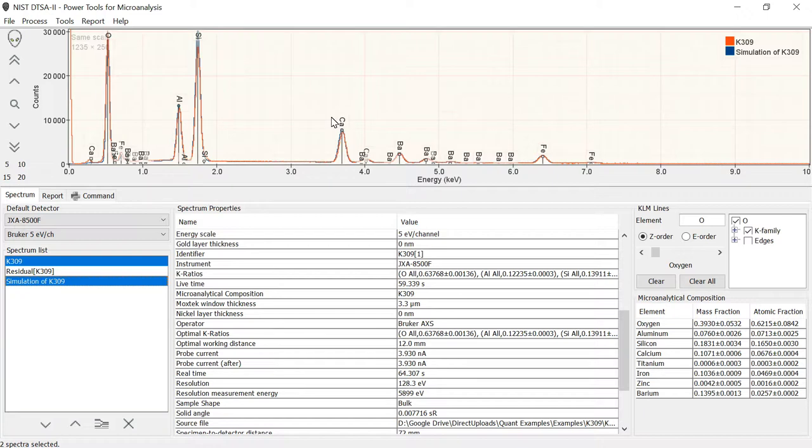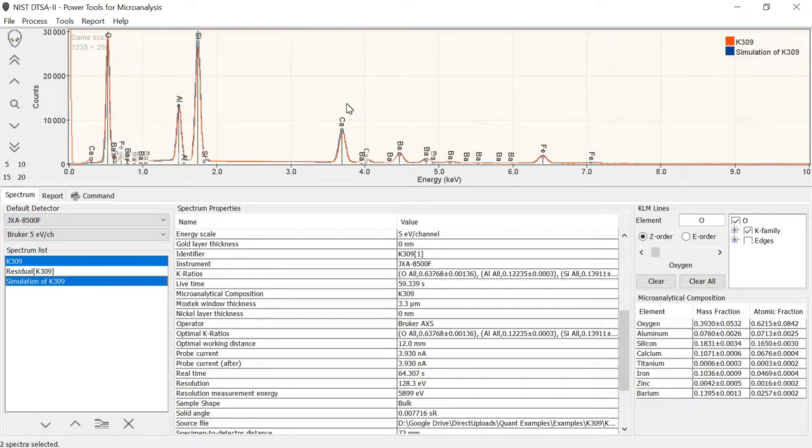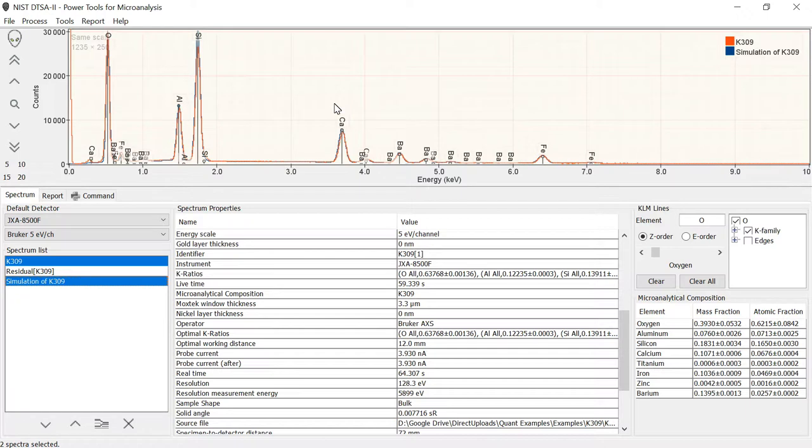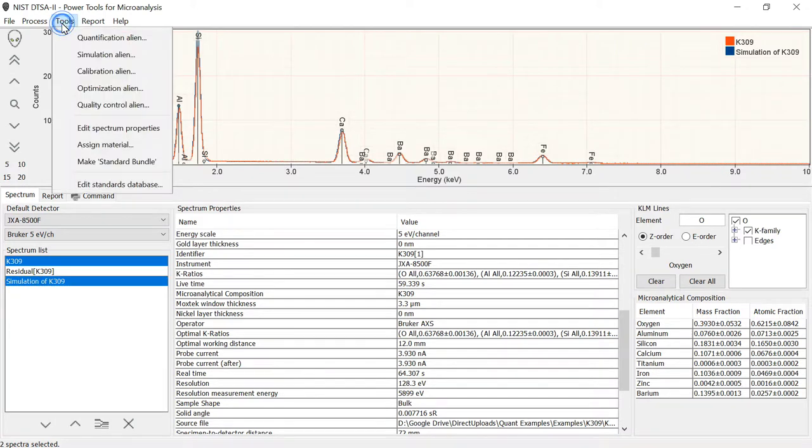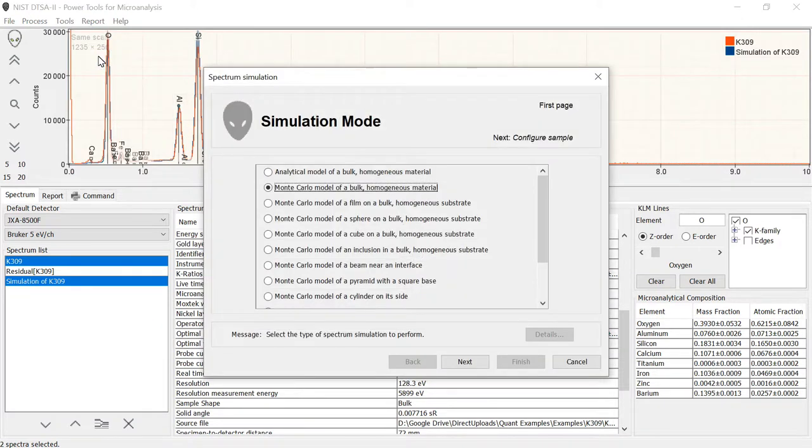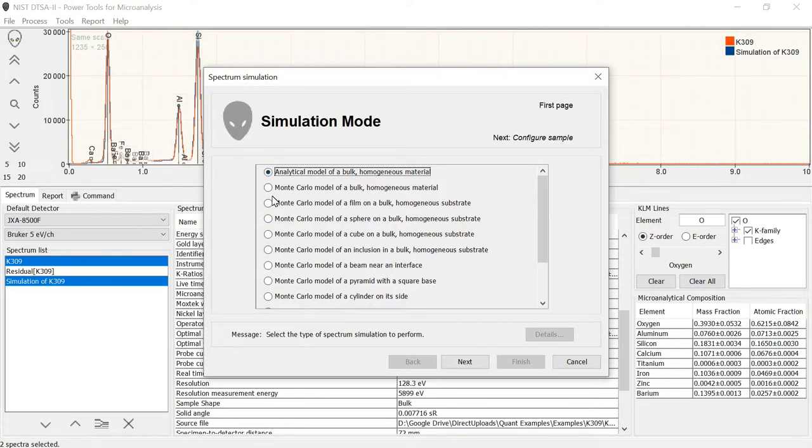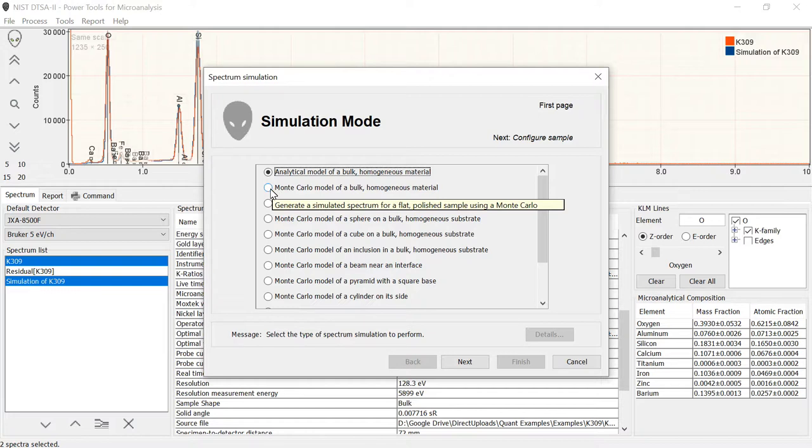This simulation here was what we would call an analytical spectrum simulation. It used the algorithm used for the phi-rho-z matrix correction, which is called XPP. It's the simplified model of Pouchou and Pichoir to actually perform the spectrum simulation. We also can simulate spectra using another tool. This tool is available from the tool menu and it's called the simulation alien. The simulation alien gives you various different modes. We already discussed the top mode, this analytical model, this would be the same model that was calculated here using the Pouchou and Pichoir analytical phi-rho-z curve.